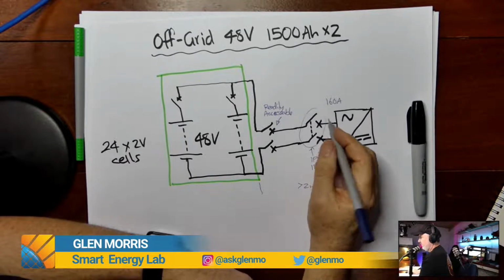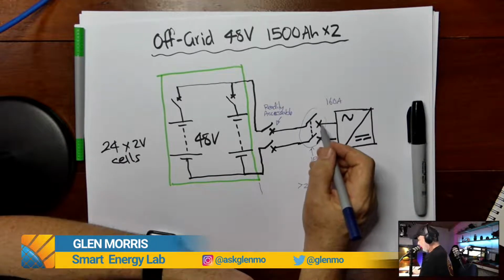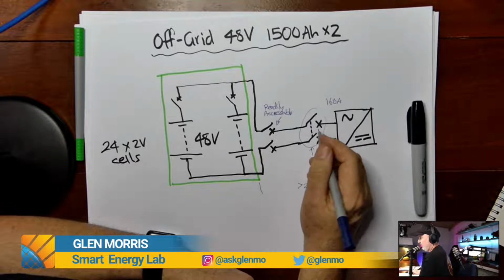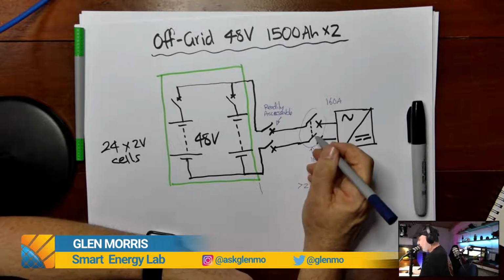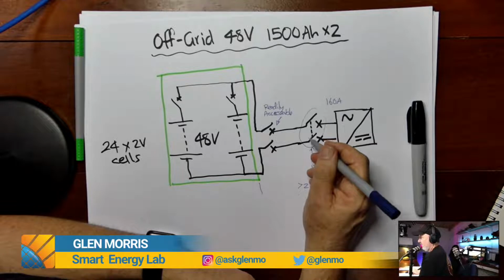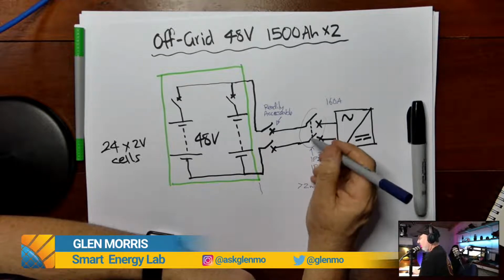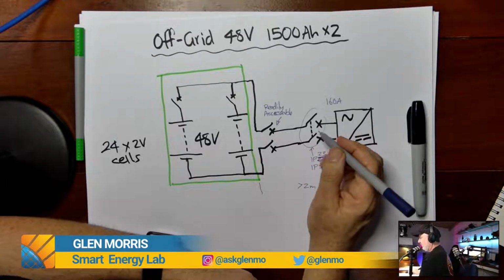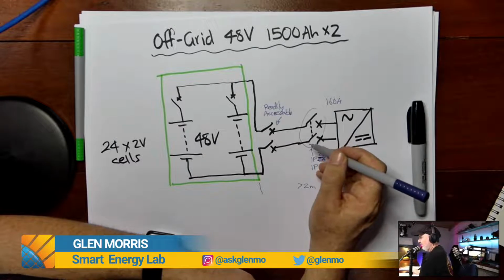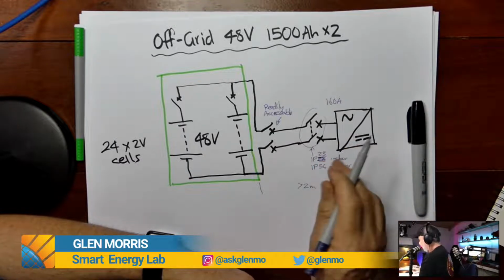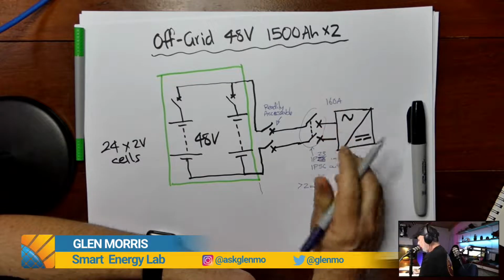Something to consider too is running very close to the limit of a circuit breaker rating. So say we did put in a 160 amp circuit breaker in here, it may well be, depending on what the ambient temperature is, derating somewhat because of temperature, and it could false trip, so you probably want a bit of headroom above that.